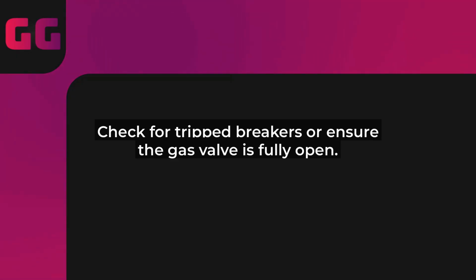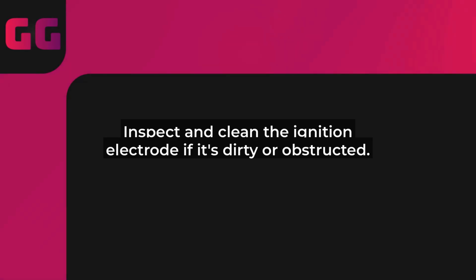Next, inspect the ignition components. Carefully look for dirt or debris on the spark electrode. If it's dirty, gently clean it with a soft brush. Also, ensure there's no blockage in the flue or condensate pipe, as this can prevent proper ventilation. If you're comfortable, you can use a multimeter to test the flame sensor for continuity, but if not, it's time to call in a professional.